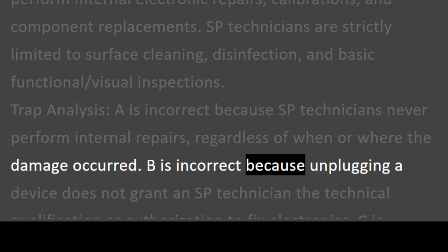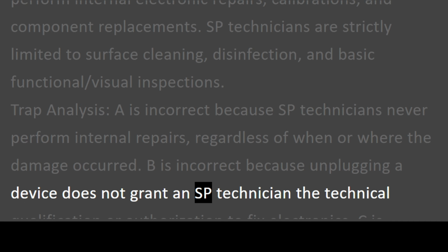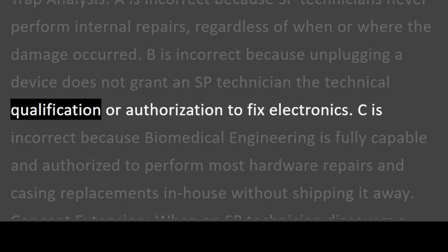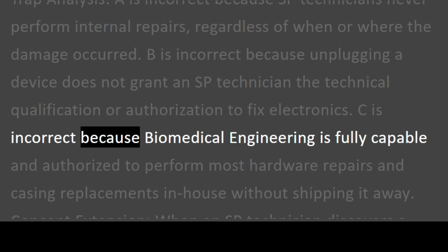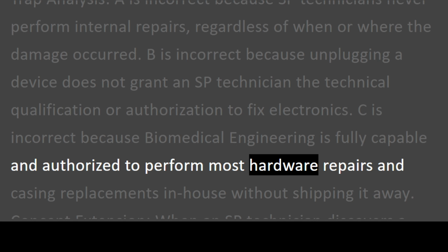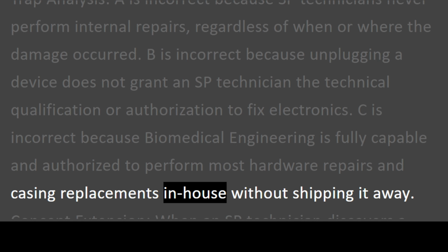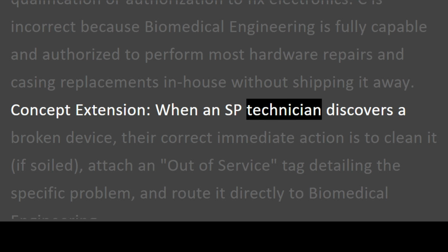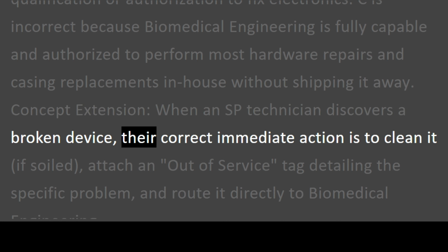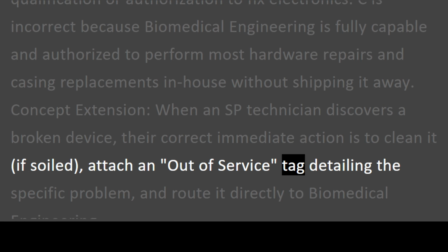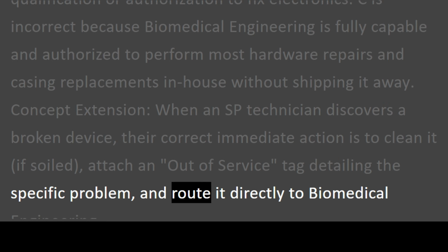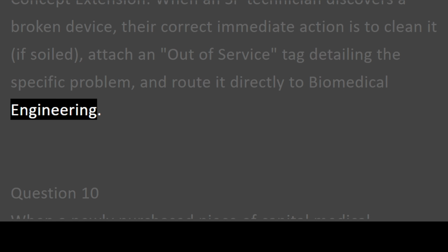B is incorrect because unplugging a device does not grant an SP technician the technical qualification or authorization to fix electronics. C is incorrect because biomedical engineering is fully capable and authorized to perform most hardware repairs and casing replacements in-house without shipping it away. Concept extension. When an SP technician discovers a broken device, their correct immediate action is to clean it, if soiled, attach an out-of-service tag detailing the specific problem, and route it directly to biomedical engineering.